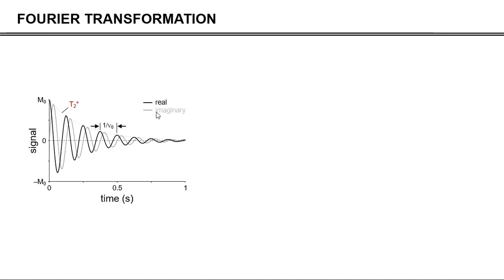You can see all the important parameters are in this FID signal in the time domain. M0, which is our thermal equilibrium magnetization, corresponds to the first point amplitude. The decay of the signal over time is governed by T2 star relaxation. And the distance between one maximum here and a maximum there is 1 divided by the Larmor frequency.